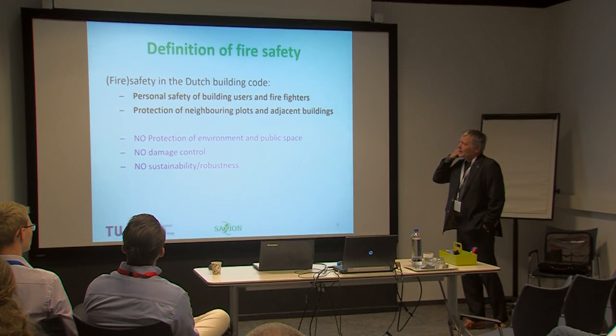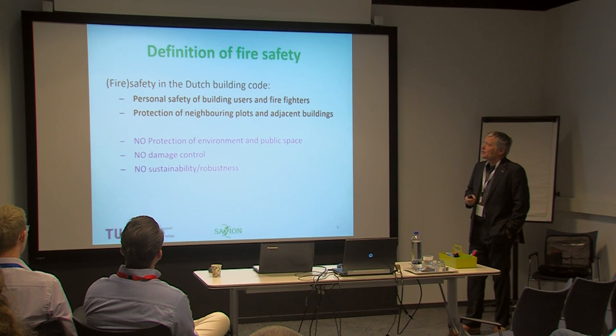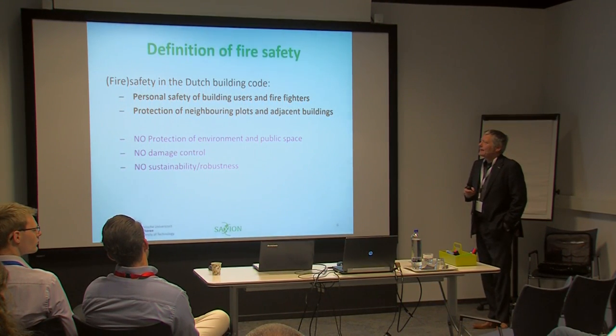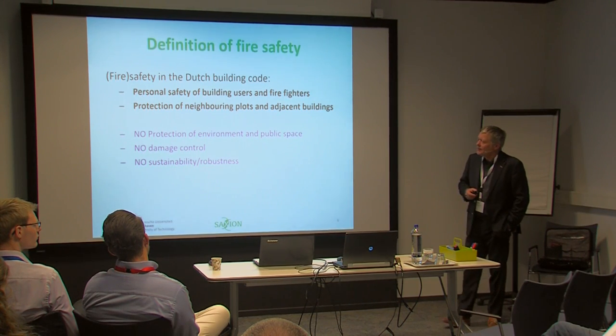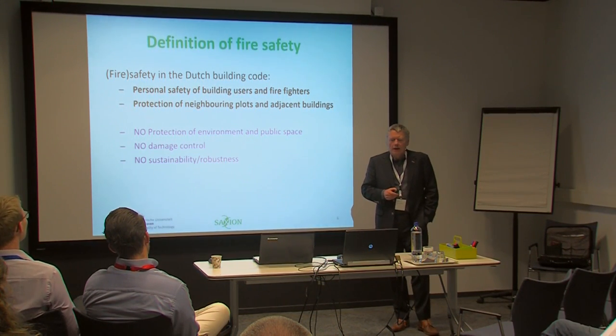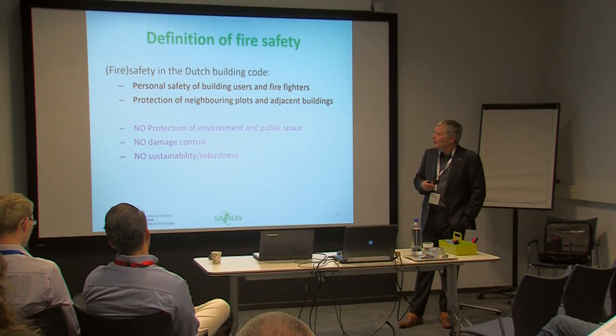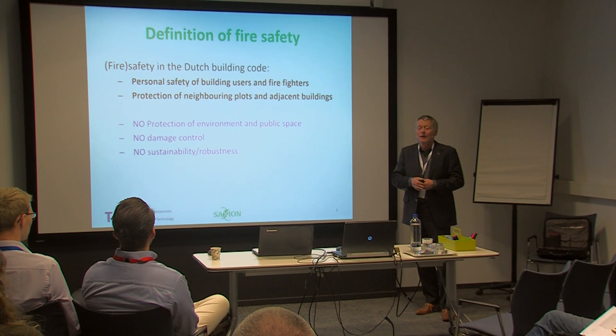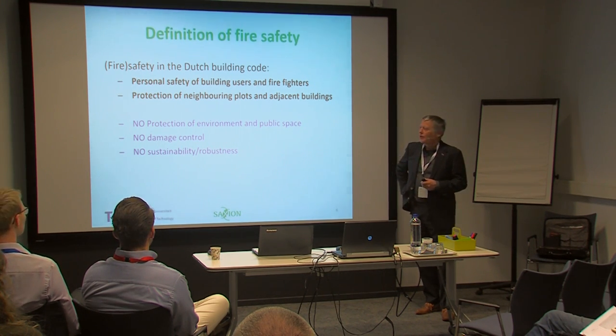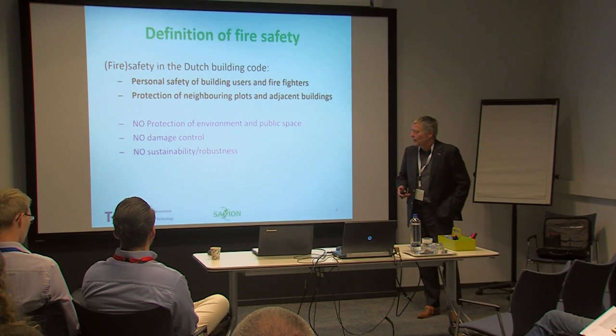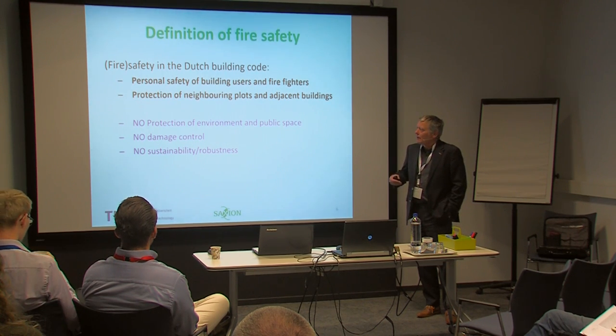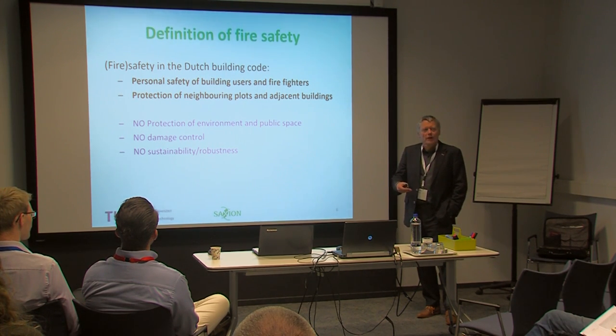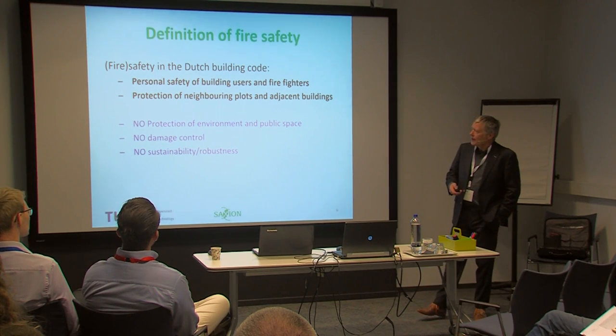Fire safety in the Dutch building code consists of a lot of practical rules and regulations, like maximum size of a fire compartment and maximum walking distances. They serve two main objectives: personal safety of building users and firefighters, and protection of neighboring plots. There is no damage control in the building code. That's where the Saxion students' case comes in — it makes sense to do something about damage control, especially for resilient buildings regarding sustainability and robustness. These are private objectives not in the building code; you have to formulate them yourself.